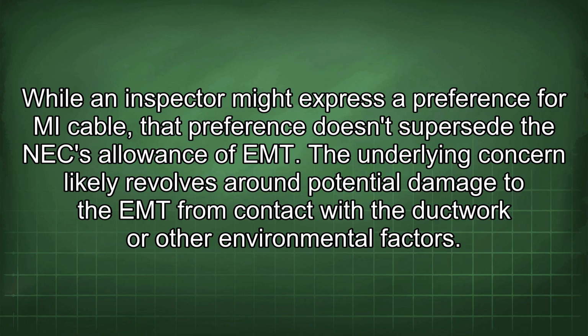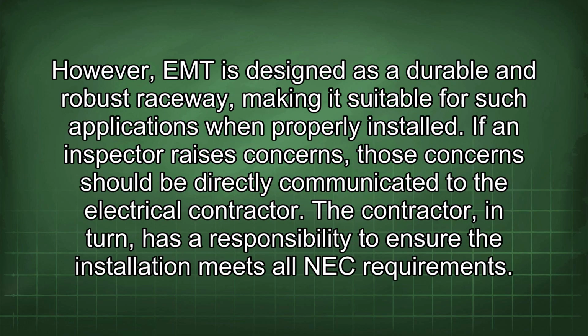The underlying concern likely revolves around potential damage to the EMT from contact with the ductwork or other environmental factors. However, EMT is designed as a durable and robust raceway, making it suitable for such applications when properly installed. If an inspector raises concerns, those concerns should be directly communicated to the electrical contractor. The contractor, in turn, has a responsibility to ensure the installation meets all NEC requirements.